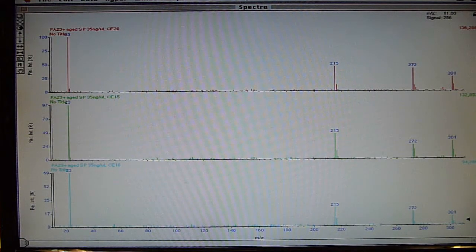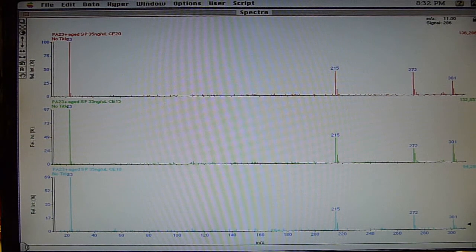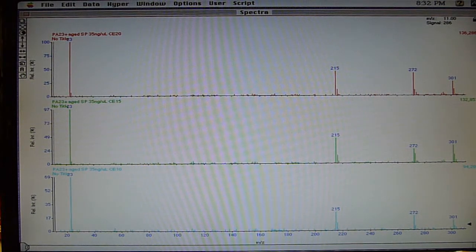And the time saving advantage, as was demonstrated, instead of having to do a MS-MS product ion scan of 301, and then 272, and then 215, and all sorts of other ions that are in the electrospray ion source, you can just set it up to do a precursor scan, and you can single out what ions are of significance to you. Now, in this example, sodium was of significance, of interest to me. And so I was looking for what are the ions that are significant that have sodium in its construct.